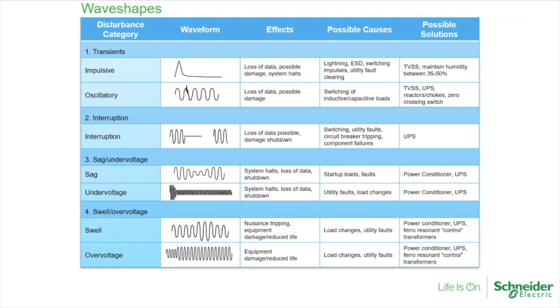For sag and under voltage, as well as swells, system halts, loss of data, and shutdown are common between most of them. For sags, startup loads can cause a sag, and faults, as well as load changes. Having a power conditioner or UPS gives you ride-through capability when you have a sag or under voltage event. And swells can be caused by nuisance tripping, or damaged equipment not operating correctly. Possible causes can be load changes and utility faults. Similarly, a power conditioner, uninterruptible power supply, or ferro-resonant control transformers can help.